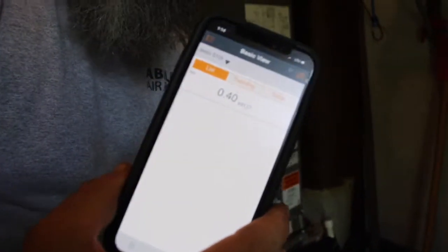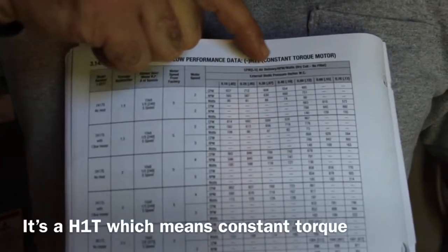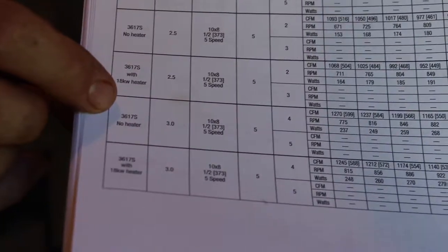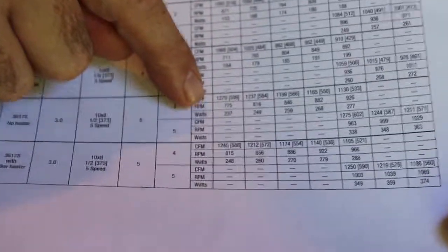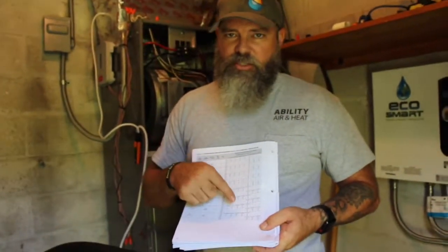We're perfectly in line with the specifications of this unit. Here's our chart for the unit. We have a constant torque motor, so it's an H1T, which means constant torque — that's an X13 motor. Right over here we have a 3-ton, and we're going to say no heat, because the other option is 18 kW and we have less than that. When we measured with the current fan speed it was 0.36, which is somewhere in between this column and this column. When we cross-reference, we're going to have 1199 to 1165 CFM.